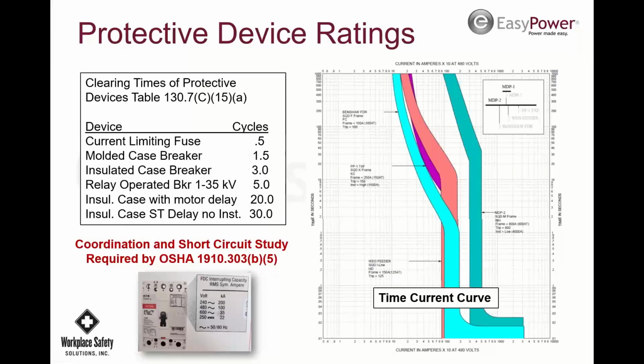So a lot of maintenance people that I've seen, as we're doing studies, we see panels that were added on, small sub panels for test areas and different kinds of things. And they go to Home Depot and get a main breaker and some panels, and then it all looks hunky-dory. It all works, powered up, everything's good, looks great, but it's going to blow up if there's a fault, and it's not going to operate the breaker within the time current curve. So that means the arc flash level can be much higher than what is calculated, even if you did do a study. So this coordination and short circuit study is very important, and this is part of doing an arc flash analysis.